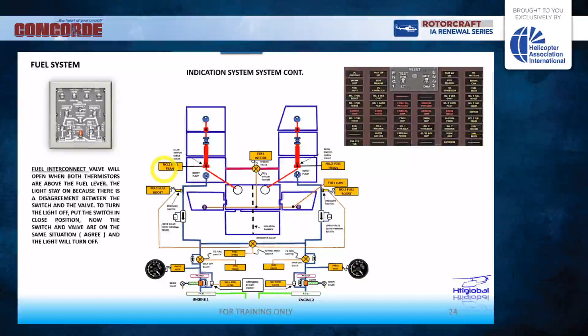In other words, when the system opens the valve, it's telling the pilot, hey, I opened a valve, do you want to keep it open? He takes the switch and puts it in the open position and the light extinguishes. Or if he prefers to override it closed, he can do that and the light continues to be extinguished. Why? Because the switch is in the same position as the valve. That's how we call it the disagreement light.